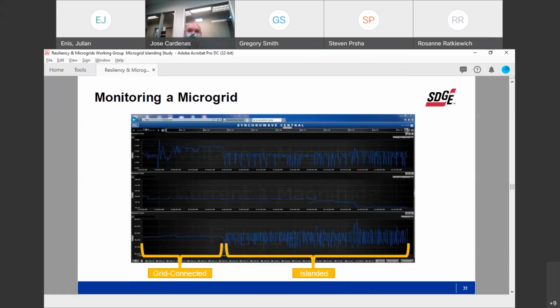I'm sorry, frequency. Sorry about that. So yeah, it's a frequency envelope. Pretty much when the frequency starts going up, the generator is going to ramp down to bring the frequency back down. And then once it gets to the bottom end of the envelope, it's going to ramp up to bring the frequency back within those bounds. So you'll see this oscillation back and forth of the frequency when you're in your island.